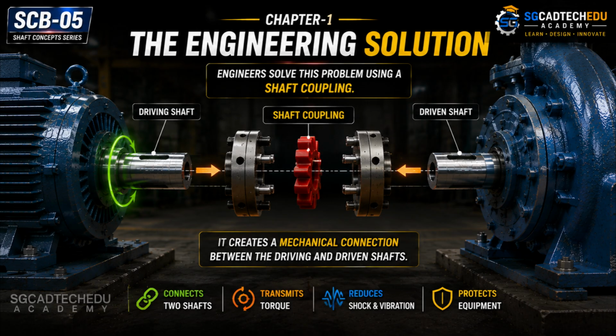Once both shafts are connected, torque can be transmitted safely and efficiently from the motor to the driven machine. Depending on the application, a coupling can also absorb minor misalignment, reduce shock and vibration, and help protect valuable equipment from excessive loads. This is why shaft couplings are an essential part of almost every rotating machine used in industry.